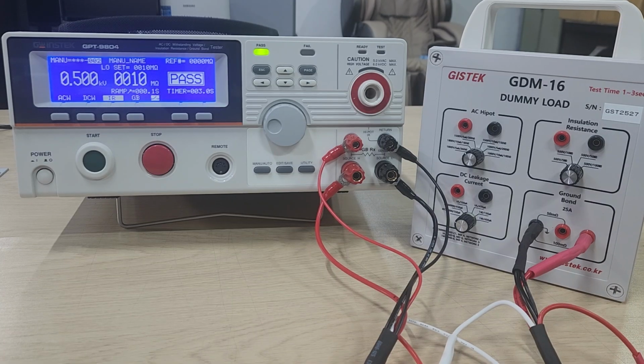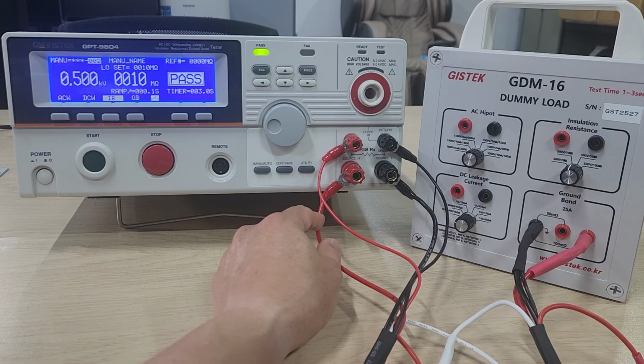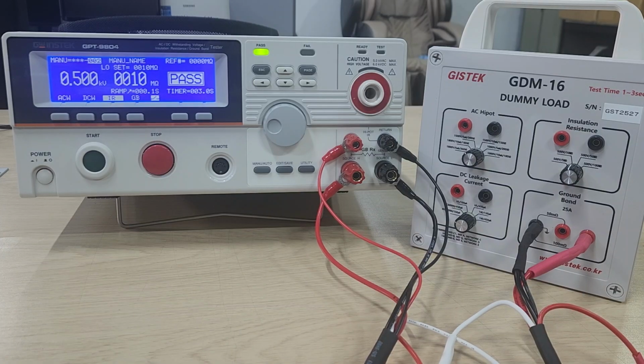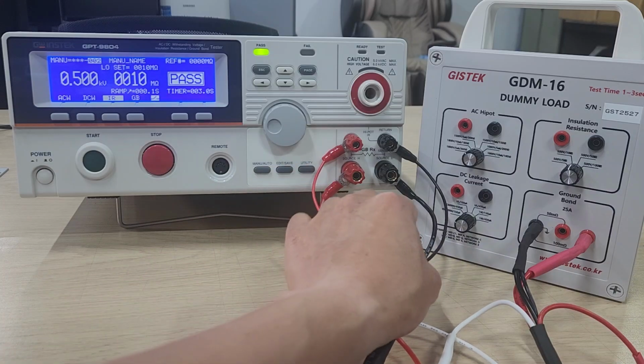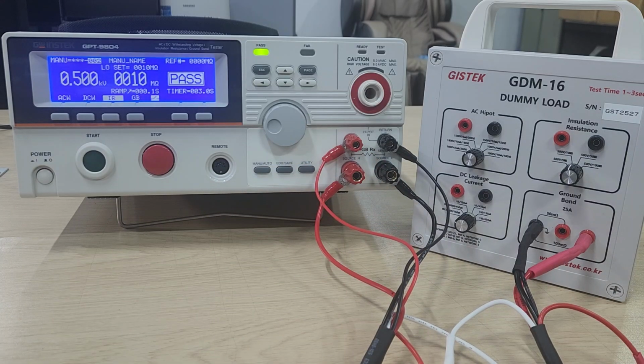The red cable, these two red cables, and the black cables are return cables. Depending on thickness, the thick cables, these two, are used to flow 25 ampere, while the thin cables, these two, are used only to measure the resistance value.